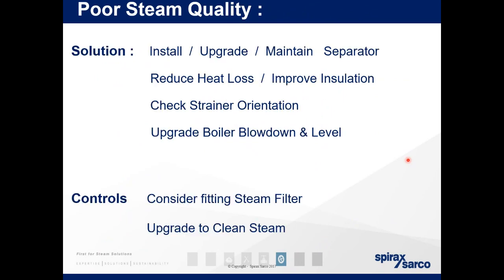So the solutions: install, upgrade and maintain separators. So as we've talked about, separators are important. Separators are cheap in comparison to, say, control valves and other equipment. So to install a separator before a control valve would be best practice, simply because you want to maintain that control valve and make sure that you have to repair it as little as possible. As I said, control valves are expensive. Protect the equipment you've got.